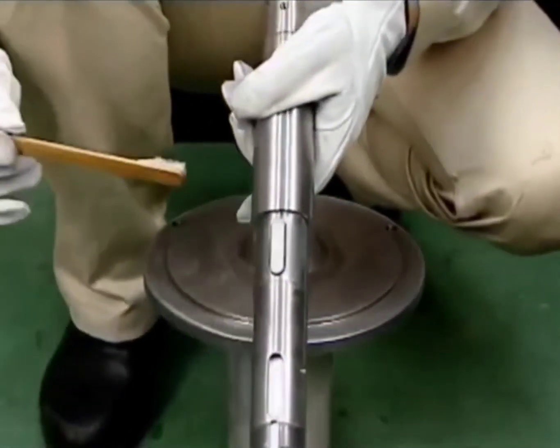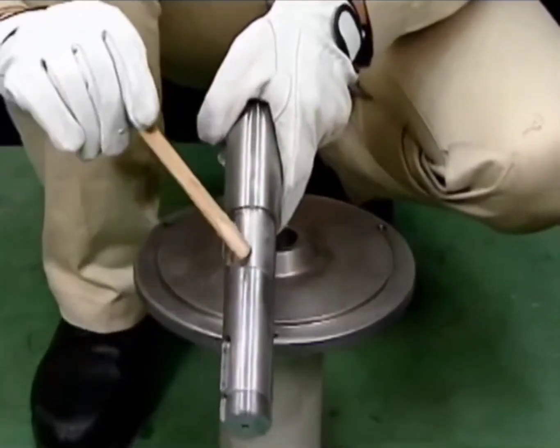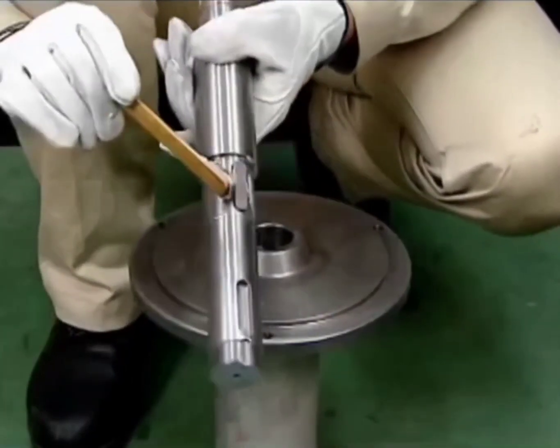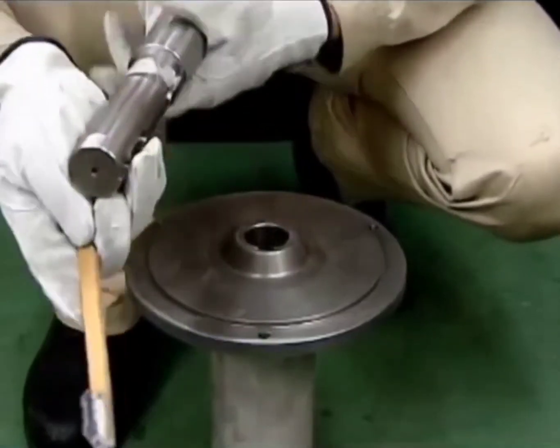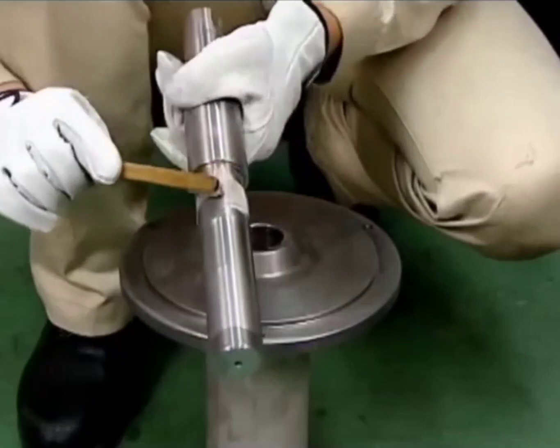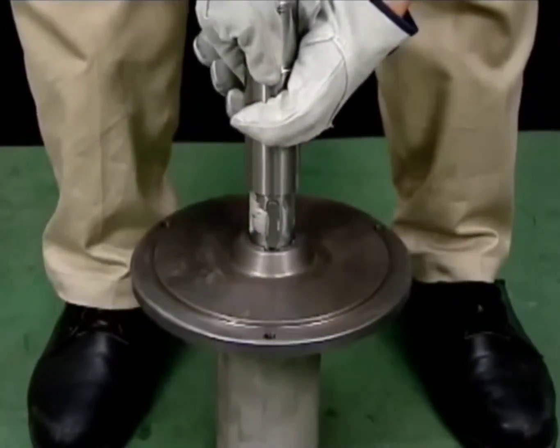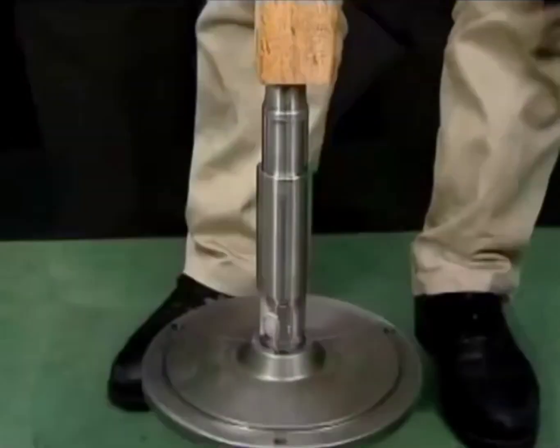Apply lubricant to the engagement part of the horizontal shaft and align with the key, then tap the horizontal shaft from the pump side. As when releasing the horizontal shaft, be sure to use a wooden slat.